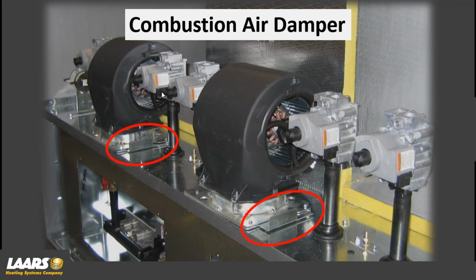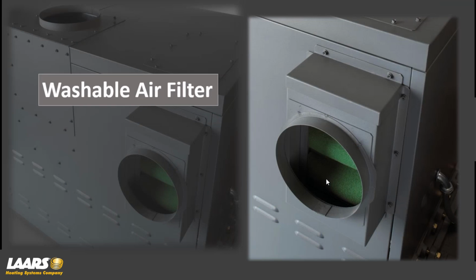The CO2 has to be at full fire. That means all gas valves are energized. So again, you want to adjust your air shutters equally. We'll go through all of this today. We also have a washable air filter. Now, the image in behind here on the Pennant boiler, you can vent in combustion air off the top or the back. On the MightyTherm2, currently it's only off the top.